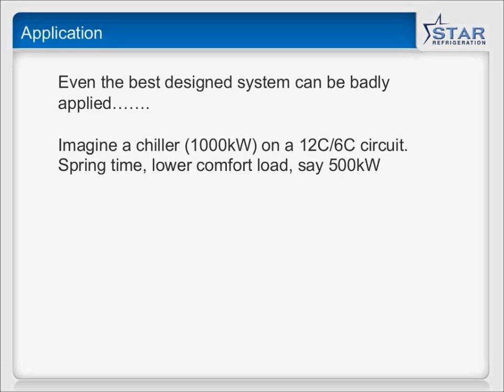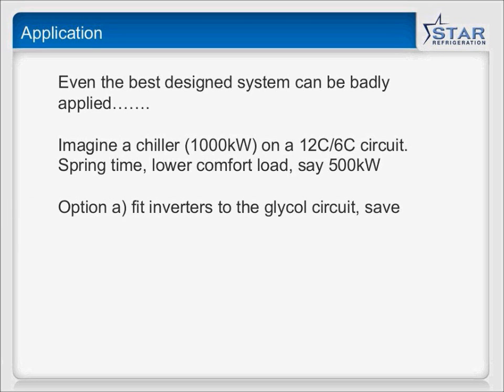So if we don't follow that rule, we put an inverter on the glycol pump, we slow it down, and we might save 50% of a 15 kilowatt drive by buying a fairly expensive drive, variable speed drive. Now in some cases it's the right thing to do, in other cases though, as I'm about to show you, maybe just setting the system up differently is better. Supposing instead of feeding out a quantity of glycol at 6 degrees and it's coming back at 9 degrees, we said, well, actually, we'll feed out the same quantity of glycol, but we'll feed it out slightly warmer. I mean, it's only common sense, really. You see it with your boiler system.